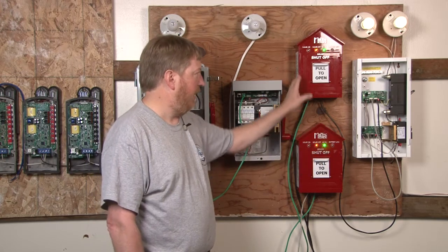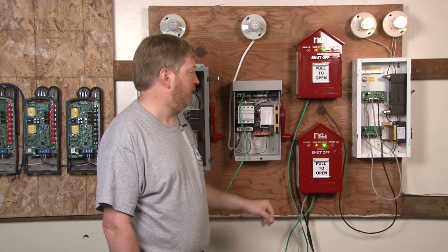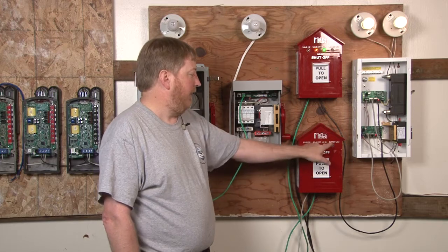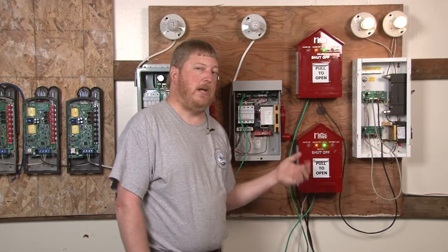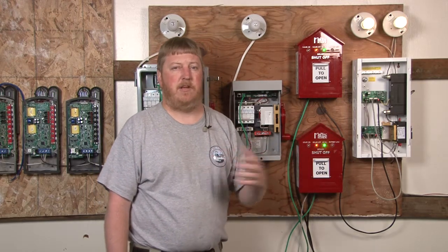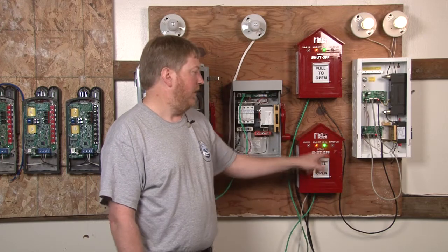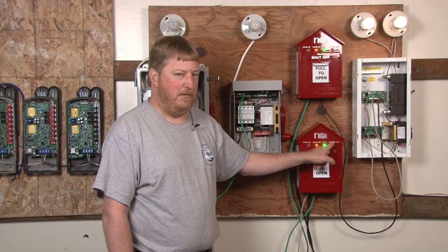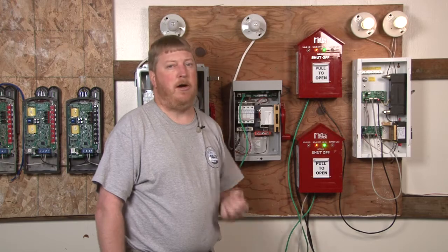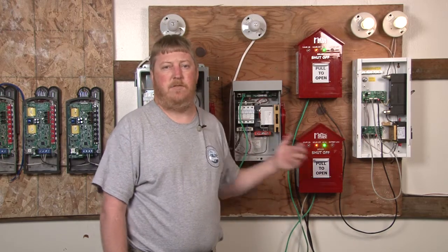AC in, we're putting 120 volts to both of these birdhouses to keep the batteries charged. And battery low: if the AC power goes away and the solar power cannot keep up, say it's been cloudy for 3 or 4 days, you might notice this light come on, meaning the batteries are low, indicating there may be a problem with your dedicated branch circuit that's feeding these.